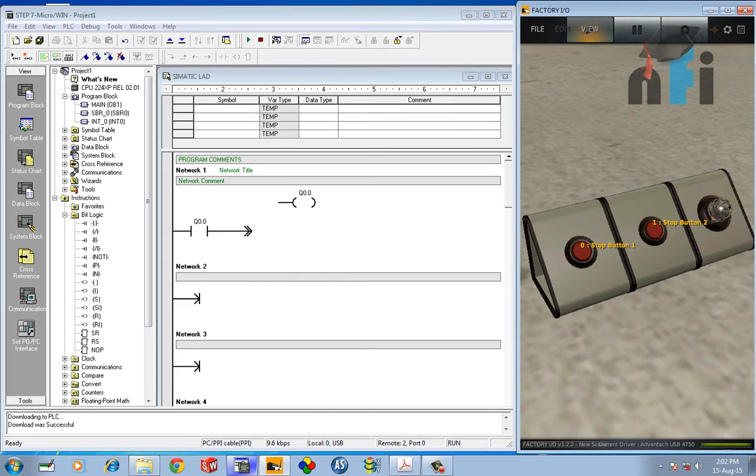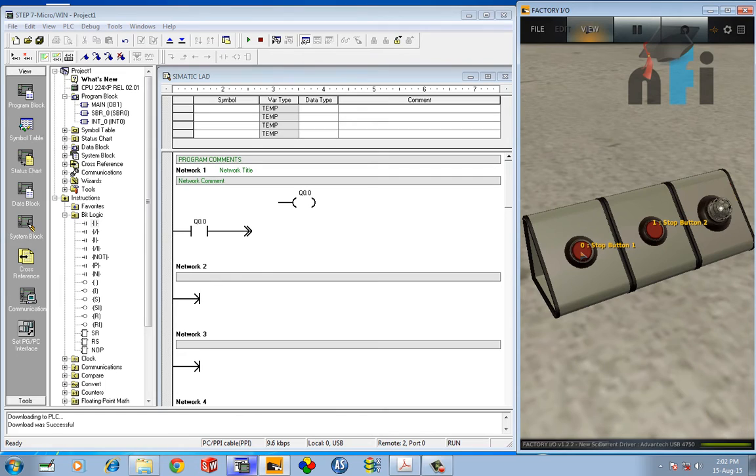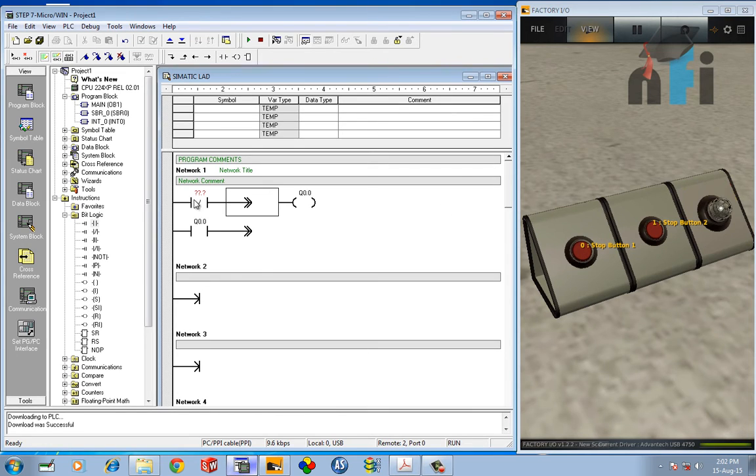Okay, and this is the indicator. Now in this case, if you want to actuate something using NC push button, we take its NC contact to turn on something. We take its NC contact. To turn off something using NC, we take its NO contact.